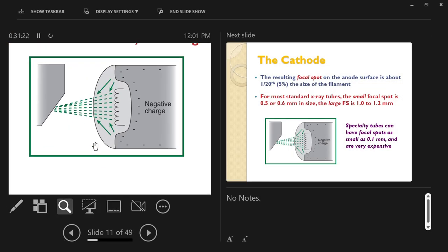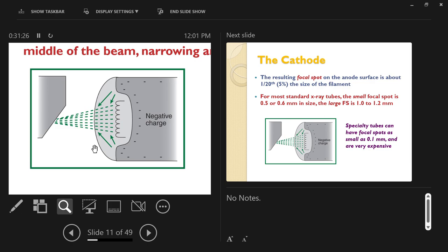Looking at the cathode from the side, with the anode disc on the left: the focusing cup wraps around the filaments on three sides and is open on the front. A negative electric charge is applied to the entire metal cathode and focusing cup. Like charges repel, so the negatively charged electron cloud is repelled by the negatively charged cup, focusing it into a narrow beam directed toward the anode face.